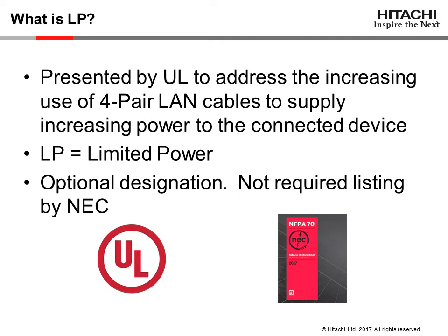Recognizing this potential problem, UL, after significant lab testing, proposed the LP designation. LP stands for limited power, and defines a cable's ability to support power without exceeding its maximum operating temperature.